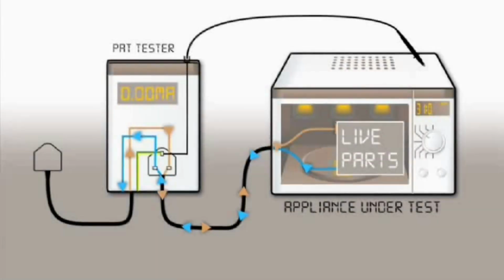The touch current test is carried out by connecting the PAT to the appliance and the test probe to any exposed metal parts. If there is a fault with the insulation, some of the current flowing in the live conductor will return to the supply via the test probe.